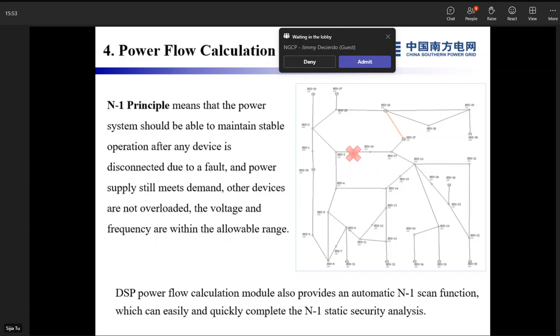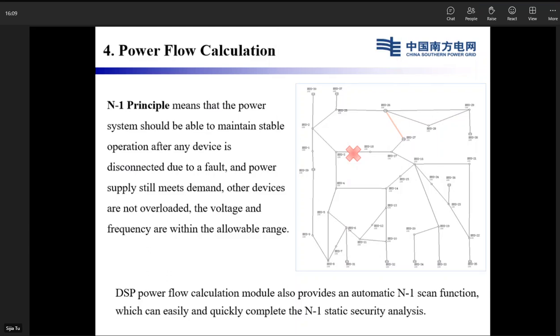DSP power flow calculation functions can also apply the N-1 principle. N-1 means the power system should be able to maintain stable operation after any device is disconnected due to a fault, and the power supply still remains. Other devices are not overloaded, and the voltage and frequency stay within the allowable range. It means any part can be cut off or disconnected from the system, and the whole system can still run normally and stably.